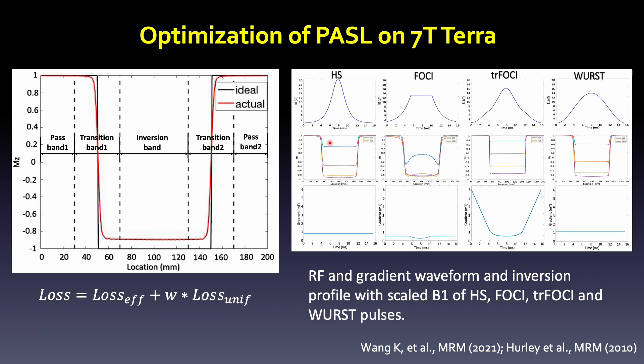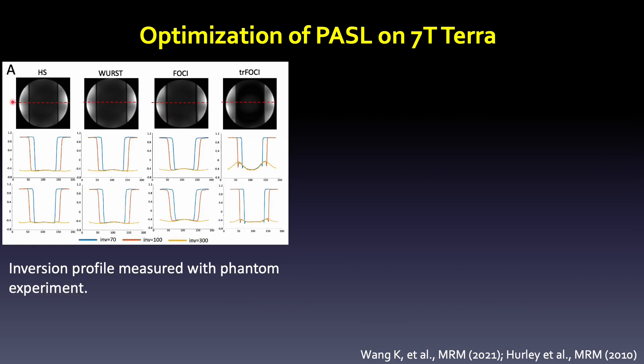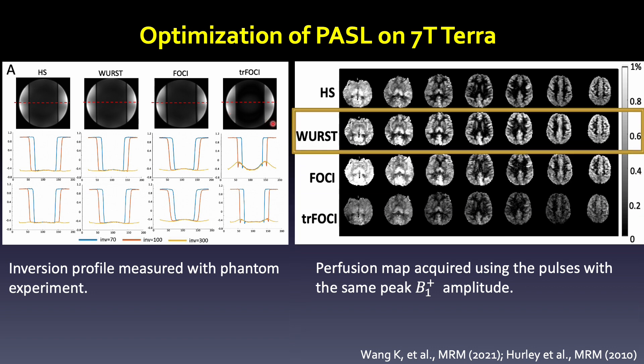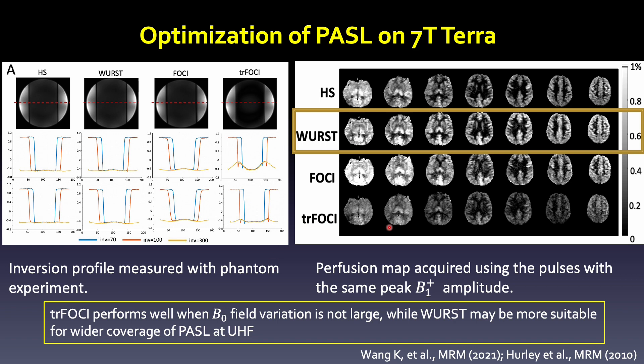Here are their waveforms as well as their simulated profiles at different B1 magnitudes. Here is the inversion profile in a gel phantom with equal SAR and equal B1 magnitude. Here are the in vivo results using these four different adiabatic pulses. Our results show that the WURST pulse performs most optimally in terms of inversion efficiency and inversion band uniformity. There is also literature showing that the trFOCI pulse performs optimally when B0 field variation is not large. Our suggestion is that WURST may be more suitable for wide coverage PASL.